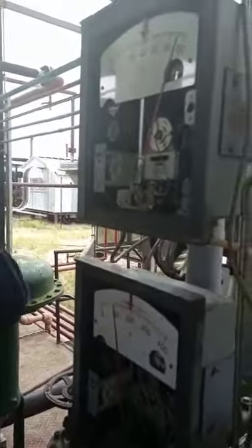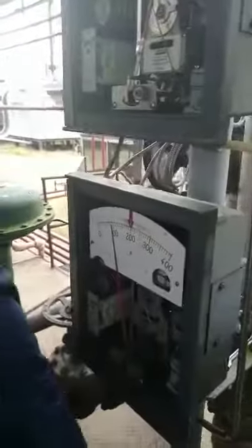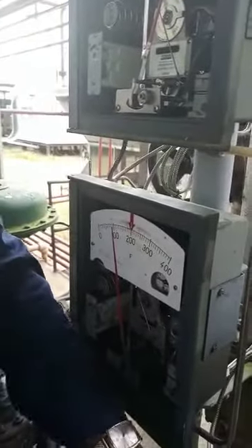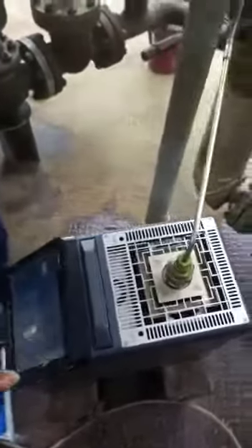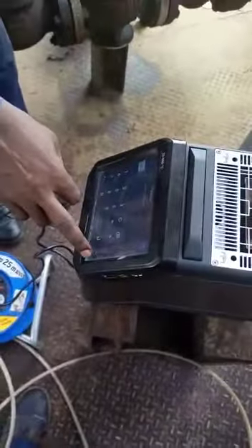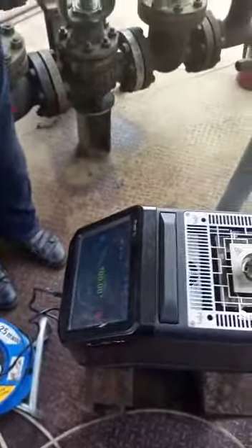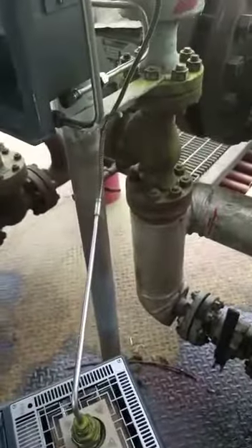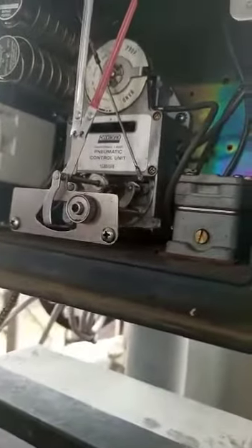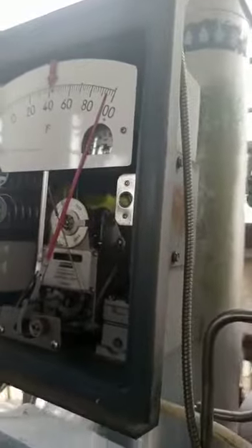Remove the temperature probe from this temperature controller, and let the temperature go back to normal room temperature. Now we are going to insert it back into the dry block so that the probe can start heating up again, to check our adjustment and whether it's corresponding to what we want. So this is at 100, and looking at this angle, it is at 90 degrees. So now the adjustment is on, so we have to check it again to see what it will give us at 100 to 100.